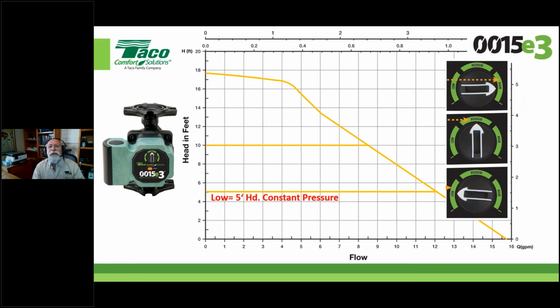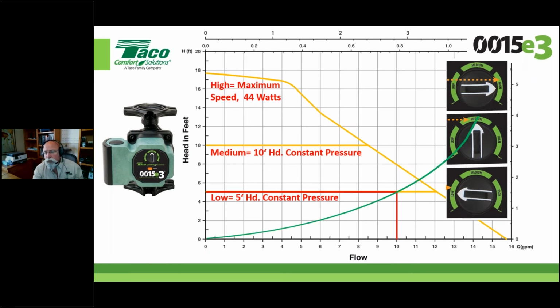Think of it this way: there's no zone valves or thermostats or actuators or anything that are going to change the hydraulics that this pump is ever going to see in a primary boiler circ application. Hopefully that rings true to everybody and you understand where I'm going with that. There's the medium head and there's maximum head. In this case, we knew we were at 10 at 5, and that's what you're going to see pretty much. It might move a little bit back and forth depending on temperature, viscosity, and some other things, or how well you did your estimate. But the beauty is I can come back this way as well. It'll just find its happy spot somewhere along this line.